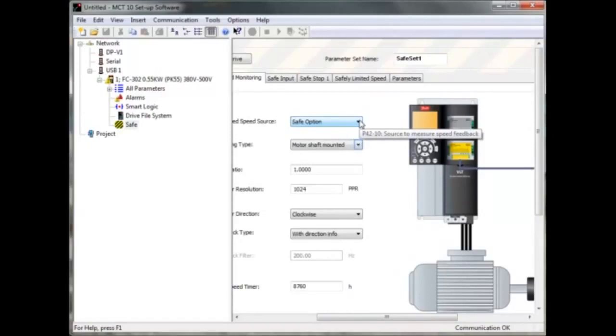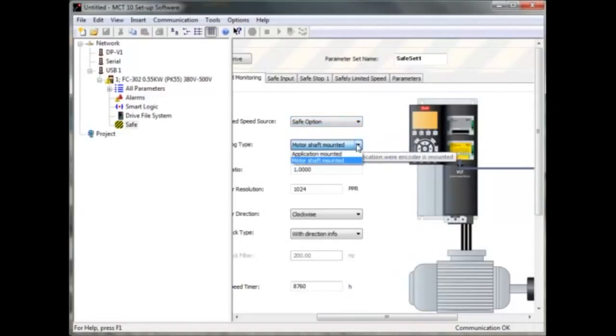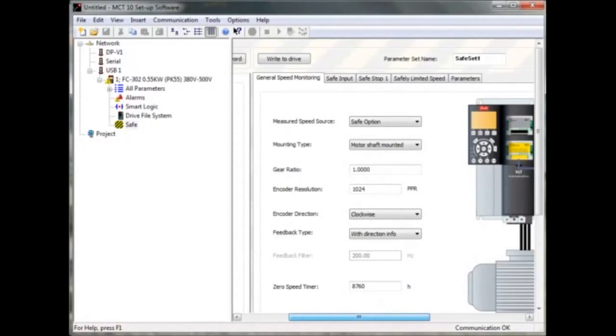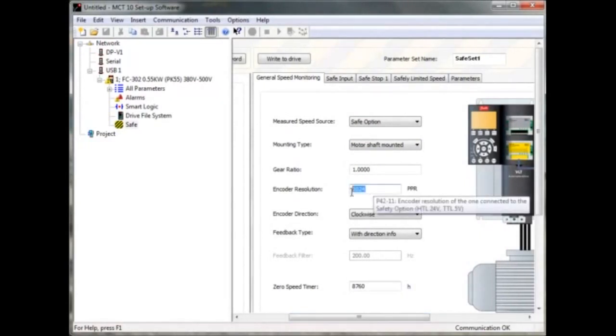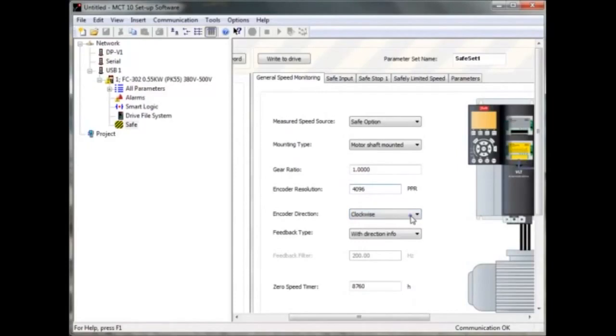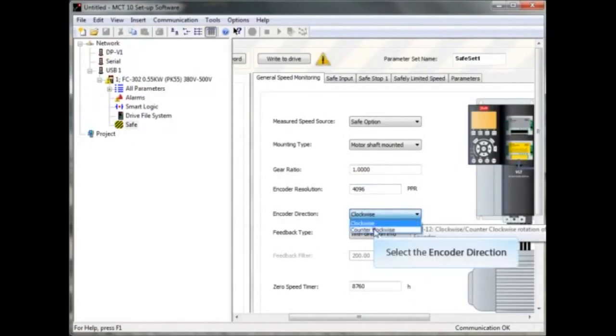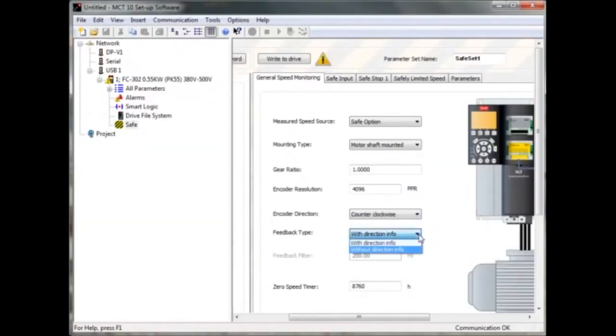Now you choose the mounted type — whether the encoder is mounted directly on the shaft or there is a gear in between. If an encoder is mounted, type in the encoder resolution. For encoder direction you can choose clockwise or counter-clockwise. The feedback type can be set with direction info or without direction info. For the feedback filter, apply the recommended value if needed; this is only possible to choose if the encoder resolution is low.